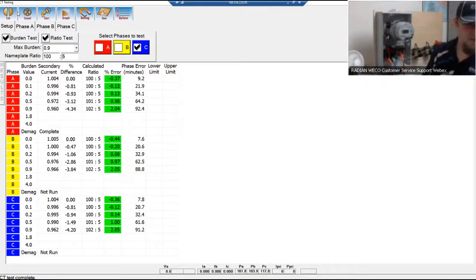Then, when I was ready to go to B, what I would do is go to my switch, open up the secondary, or not open it up, but short out the CT secondary. So this is all dead up here. Pull out my duckbill, close up my switch again. Now I want to move over to B phase, so we insert it into B phase. Throw it out so it's dead. Open up my duckbill insert here, throw that in there, unshort that to get current flow moving. And then we would test B phase and then do it again for C phase.